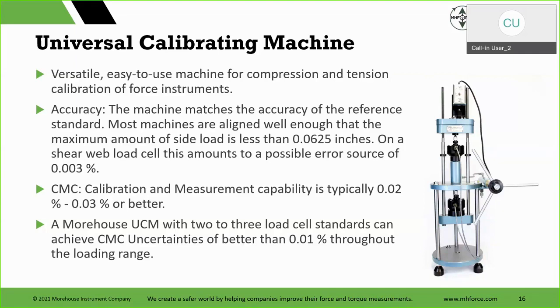Accuracy, the machine matches the accuracy of the reference standard. Most machines are aligned well enough that the maximum amount of side load is less than 0.0625 inches. And on a shear web load cell, that amounts to a possible error of 0.003%. What's nice about this machine, so to speak, and I got my highlight working, is that when we calibrate this, our yoke, everything here in this box, when we calibrate that cell, we calibrate it exactly as it showed.